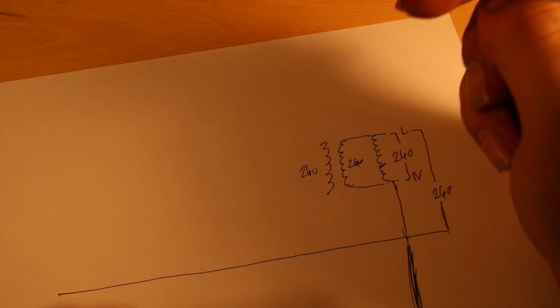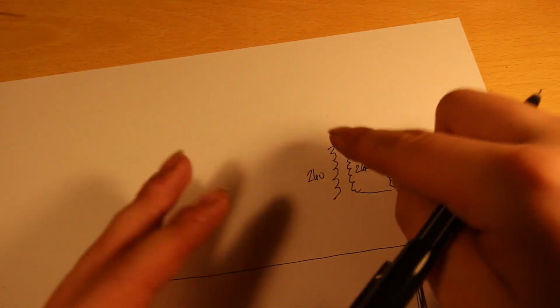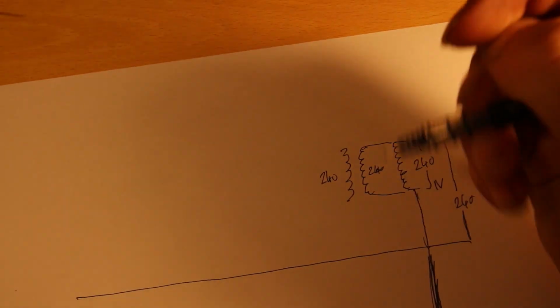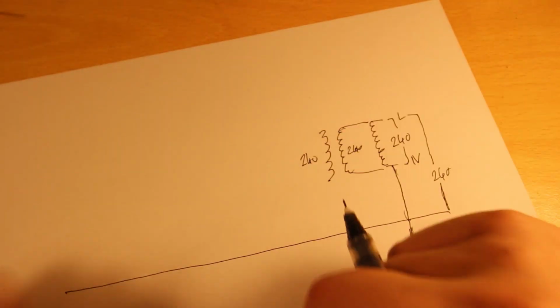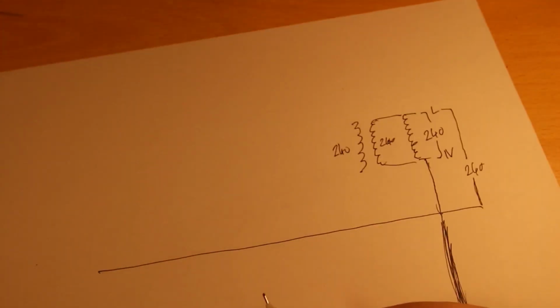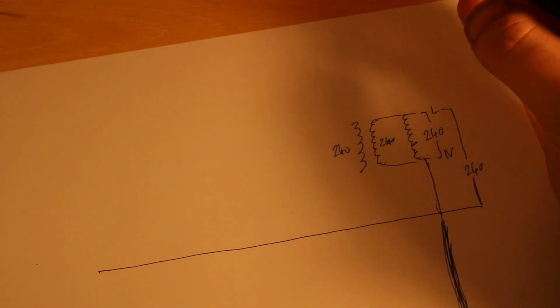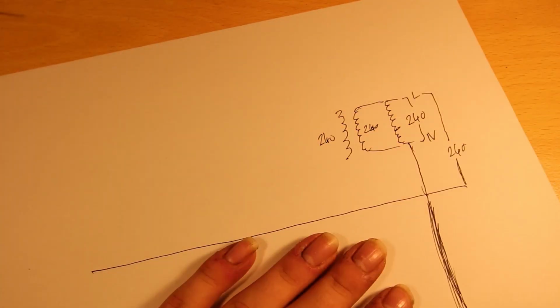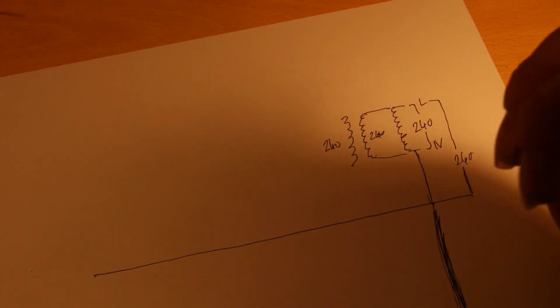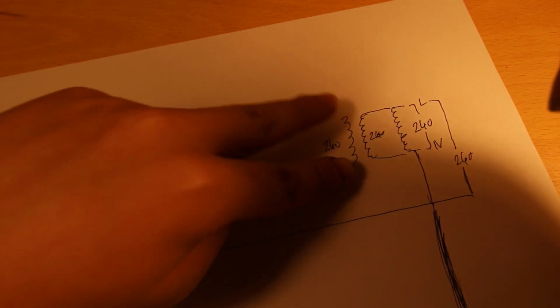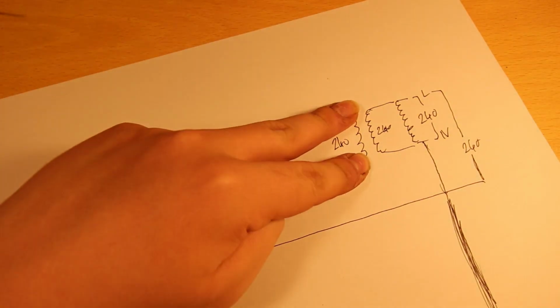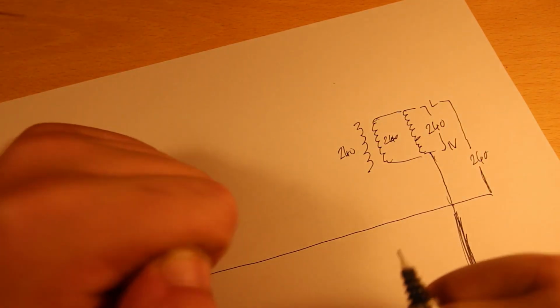It also means that you can connect measurement equipment to things and it will not blow things up by accidentally putting mains across your test equipment. But again, you have to be very careful with such things. You can accidentally reference things to things and it can cause problems. Again, keeping it simple, not going into that. So yes, it will prevent you getting a shock between the Earth and either of the live conductors. But another thing which is worth bearing in mind, if you touch both of those, you will get a shock. And an RCD or a GFCI will not work.